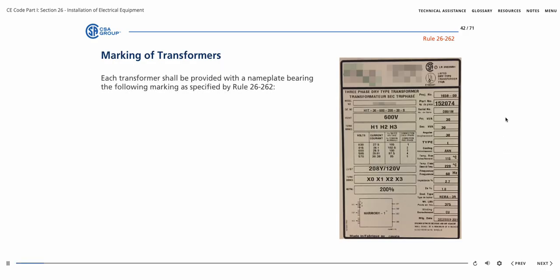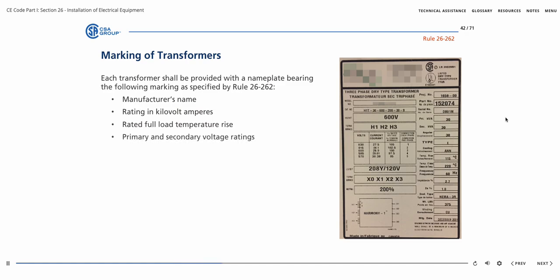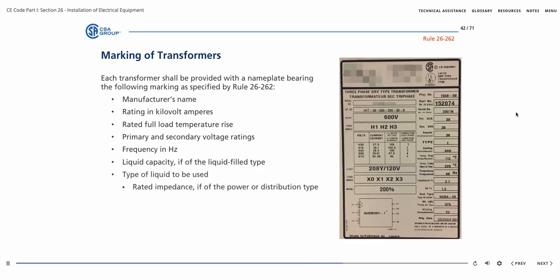Each transformer shall be provided with a nameplate bearing the following marking as specified by Rule 26-262. Manufacturer's name. Rating in kilovolt amperes. Rated full load temperature rise. Primary and secondary voltage ratings. Frequency in hertz. Liquid capacity, if of the liquid-filled type. Type of liquid to be used. Rated impedance, if of the power or distribution type, and basic impulse insulation level, BIL, for transformers rated 2.5 kV voltage class and higher.